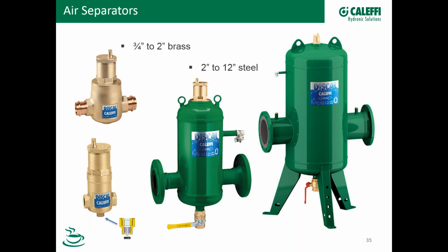So here is the family of our air separators, starting from that small compact unit you can see there. By the way, I show also that service valve down here. That same service valve can be used on the bottom of an air separator, and a lot of installations use that bottom connection on our air separator for their fill and flush connection, and also for the expansion tank. Very common use. So that compact one, we have the Discal shown with the press connections up to 2-inch in brass, and then we go into the larger steel ones.